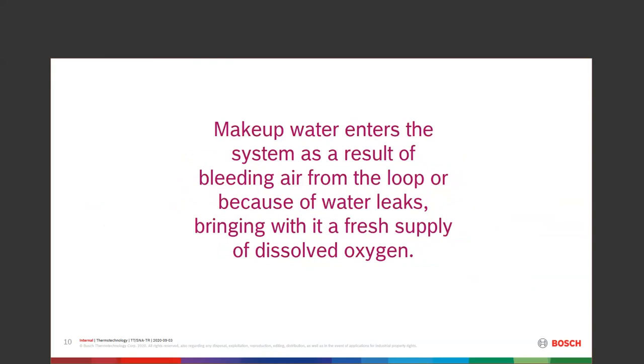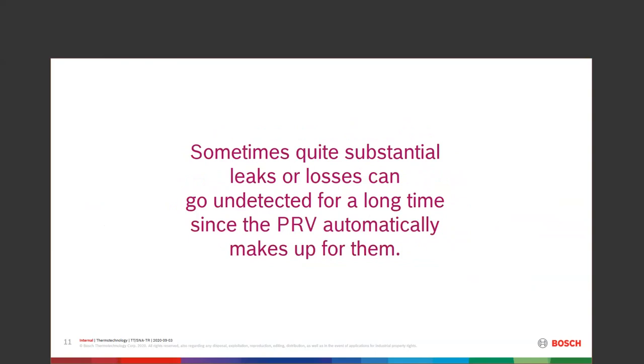With a properly maintained system we're okay. A radiant system with a leak dripping a quarter gallon per day — that's a very slow drip — under a concrete slab you won't see it unless you do some testing. It's going to make up water and dilute whatever chemicals we've put in. We have to make sure the system is tight. Periodic testing on a yearly basis — check what the water chemistry is, and if it's changed from last year, investigate why.